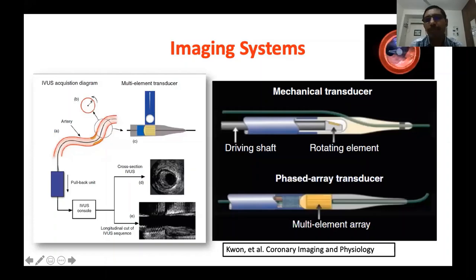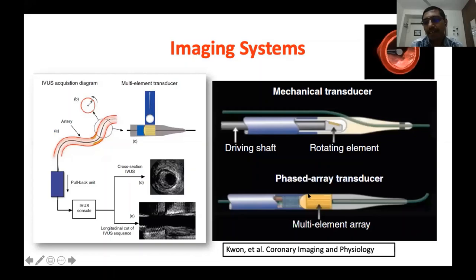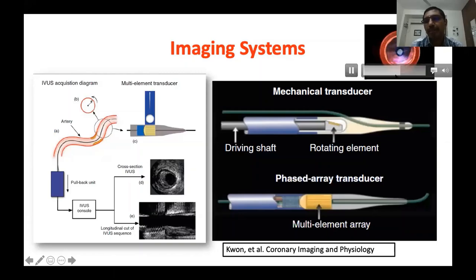There are two types of IVUS systems. One is mechanical, which has a single transducer element that goes around the circumference of the vessel to produce 360-degree images. The second is the phased array system, which has an array of 64 elements mounted on the tip of the catheter. Each element gets activated serially — the 64 elements activate in sequence to produce the 360-degree image. This is how IVUS images are produced.